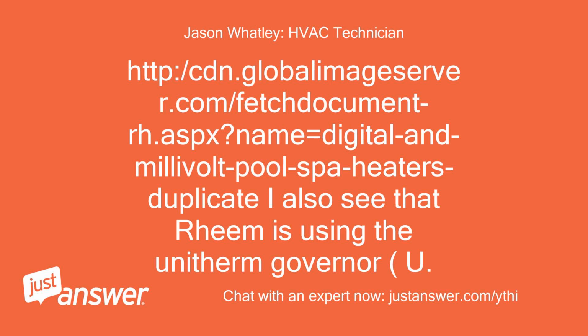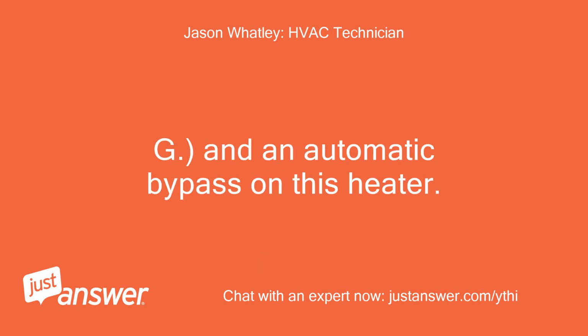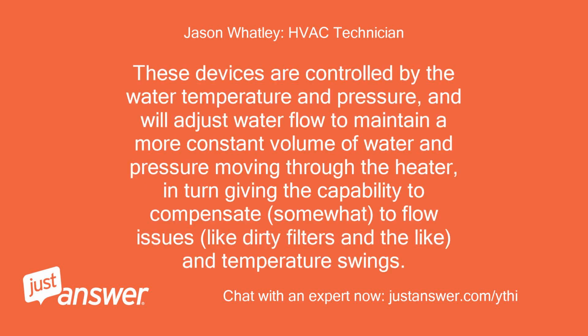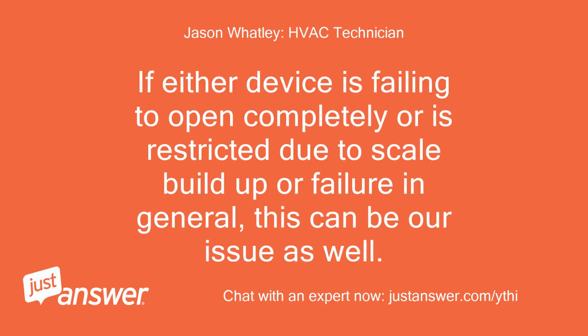I also see that Rheem is using the Unitherm governor, UG, and an automatic bypass on this heater. These devices are controlled by the water temperature and pressure, and will adjust water flow to maintain a more constant volume of water and pressure moving through the heater, in turn giving the capability to compensate, somewhat, for flow issues, like dirty filters and the like, and temperature swings. If either device is failing to open completely or is restricted due to scale buildup or failure in general, this can be our issue as well.